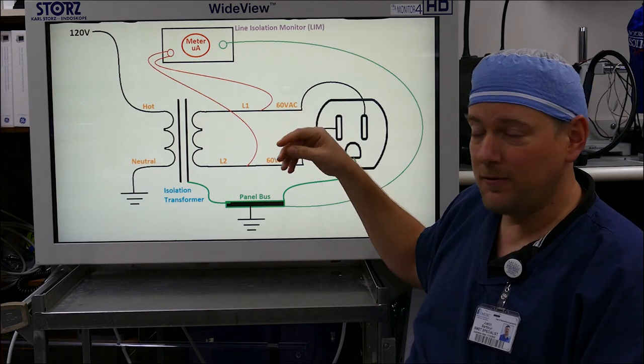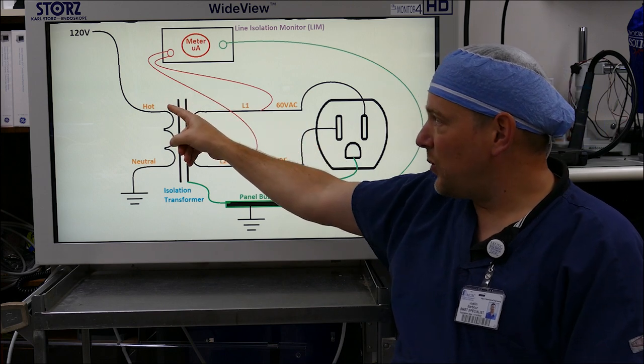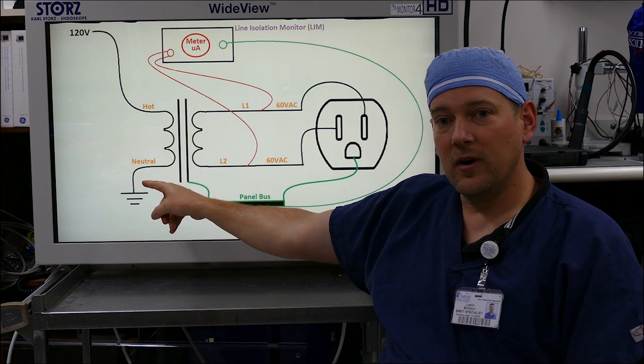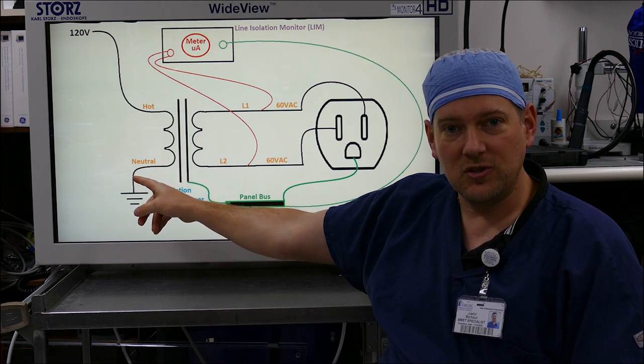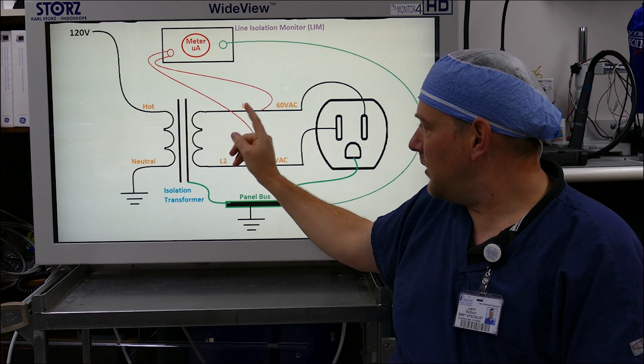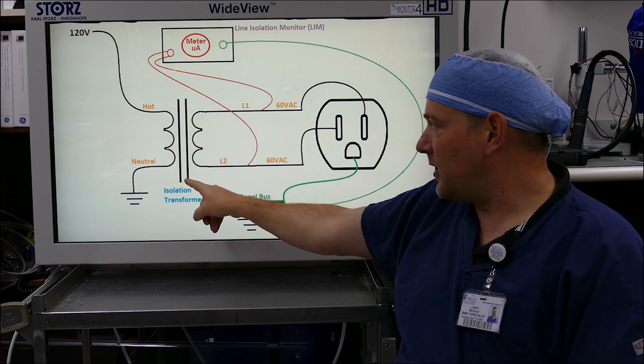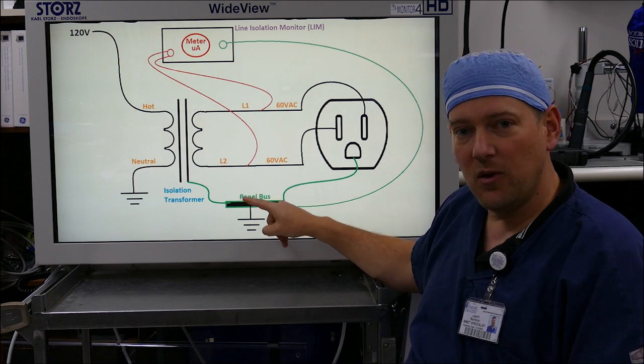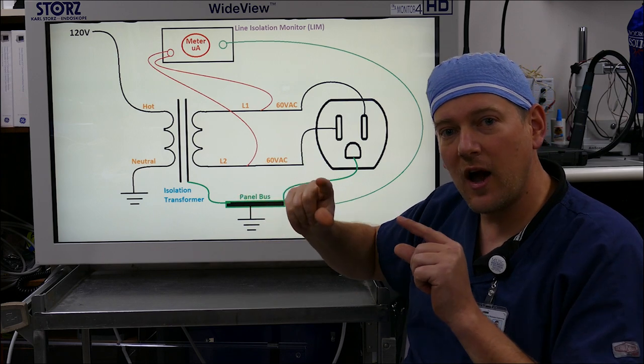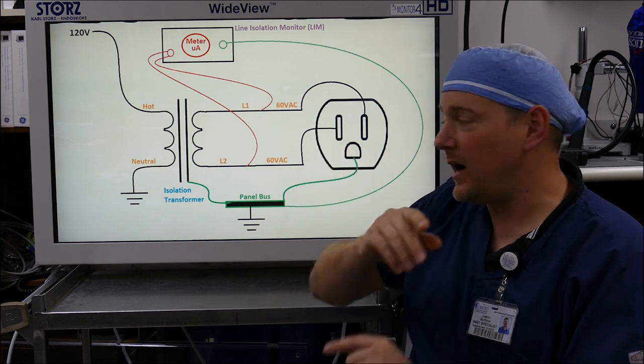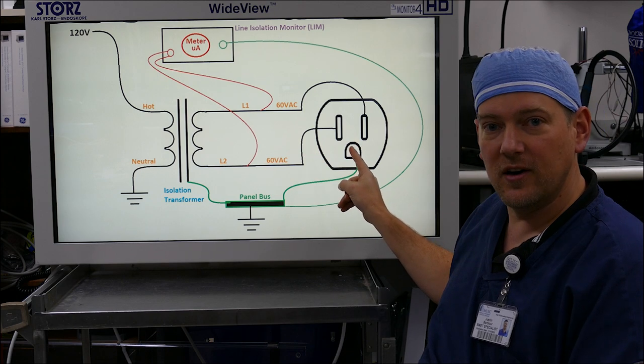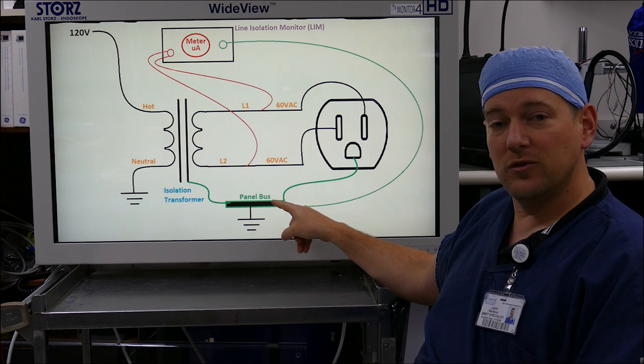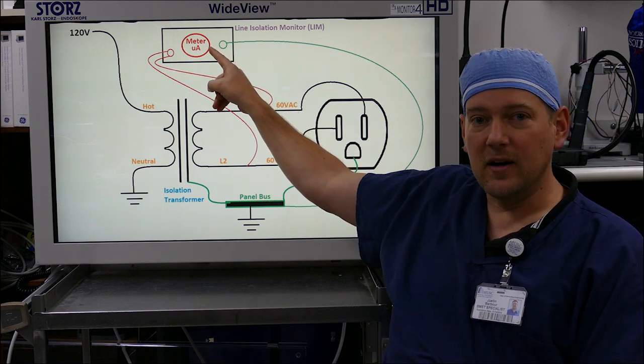So let's walk through the flow. 120 volts comes into the primaries of the transformer. The other side of the transformer is at neutral potential. You have a ground that goes from the chassis of the transformer over to the panel bus. It will be a long copper strip of all your grounds to all the electrical outlets that are in your operating room. You'll also have one wire that goes from that panel bus all the way up to a meter.